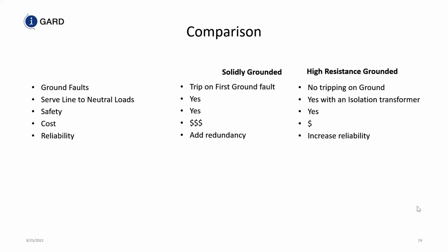Putting in a resistance grounded system is increasing reliability because you do not have to trip when there is a ground fault. And the ground fault is the most common occurrence in the electrical industry on an installation. The other benefits: reduce burning and melting effects. This is always a very good thing to happen in your electrical installation. You don't want things to burn and you don't want things to melt. So limiting the energy on a single phase to ground fault prevents burning and melting.